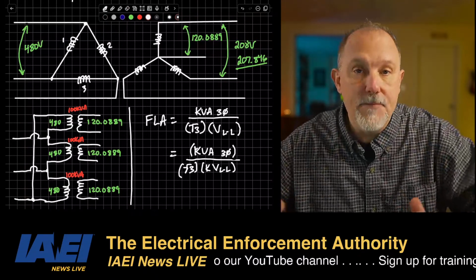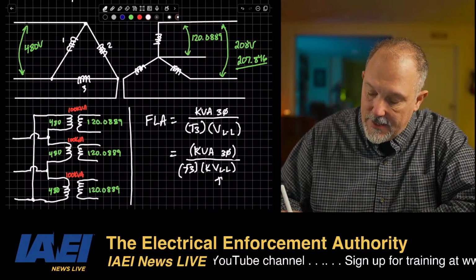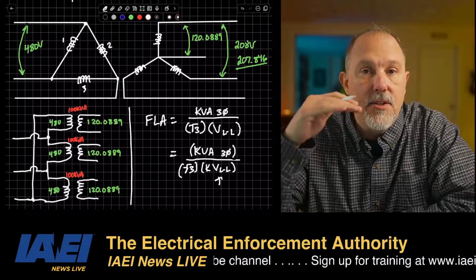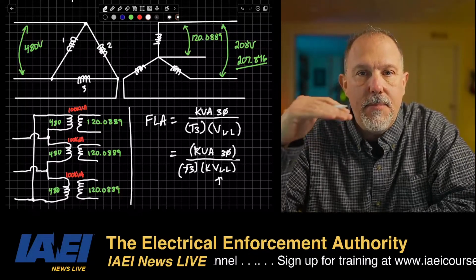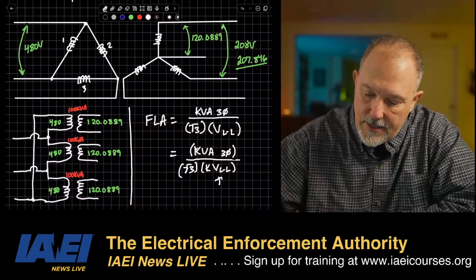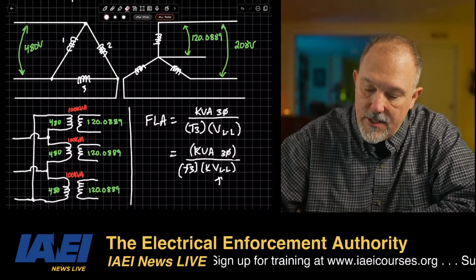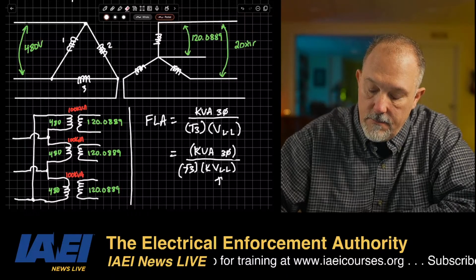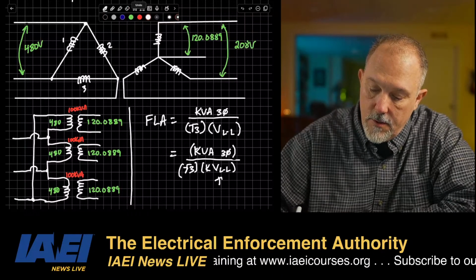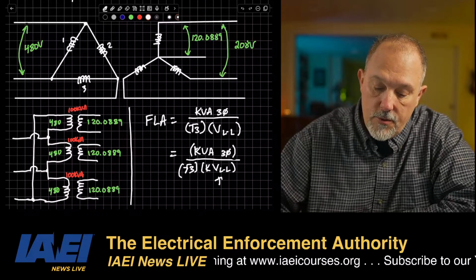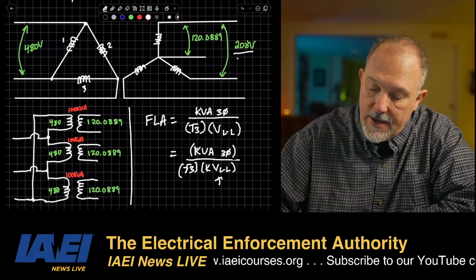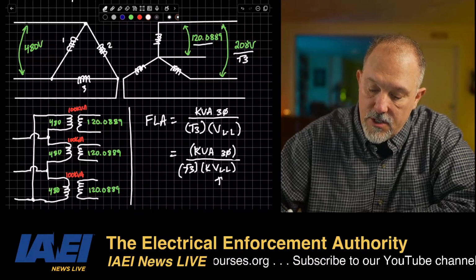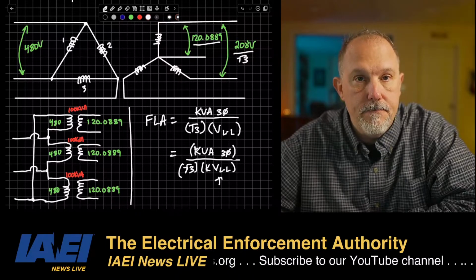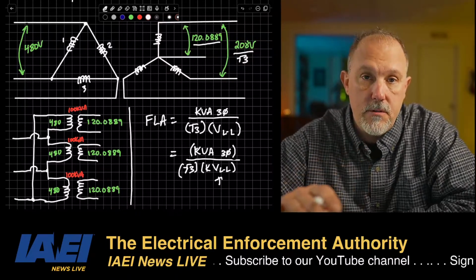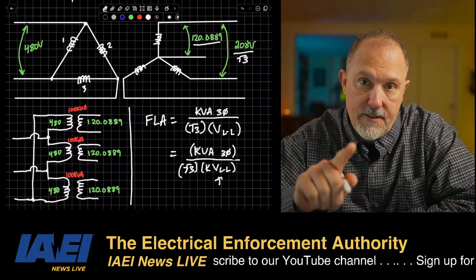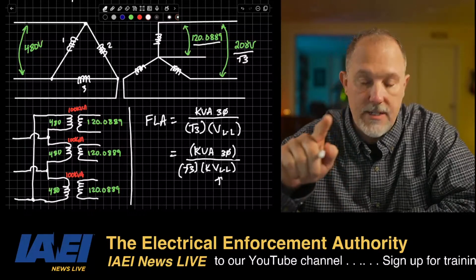Now, the reason I did that was because to get the line to neutral voltage, I'm taking the 208 volts and dividing it by the square root of 3. And that means that when I do that, 208 divided by the square root of 3 is 120.0889. It's not a solid 120 volts. 0.0889 makes a difference, and I'll show you why it makes a difference in a second.